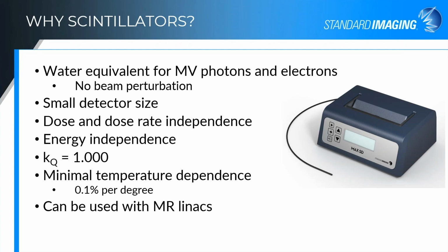And you can use these with the MR Linac as well. We make a slightly longer fiber so that the electrometer can be kept outside the 5 Gauss line, but there's nothing ferromagnetic in the detector in the fiber itself, and so it works quite well with the MR Linac.